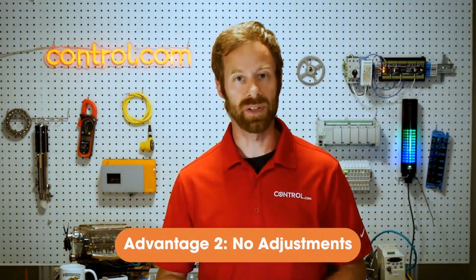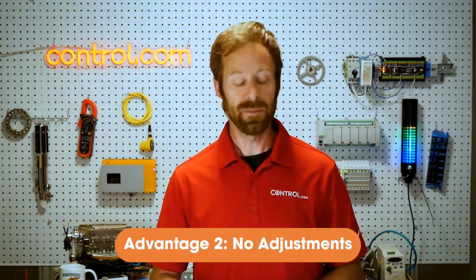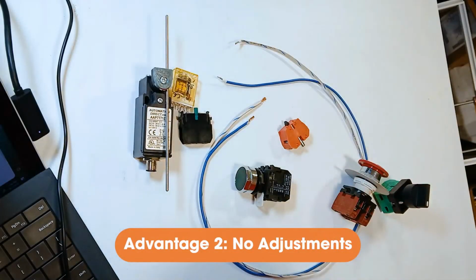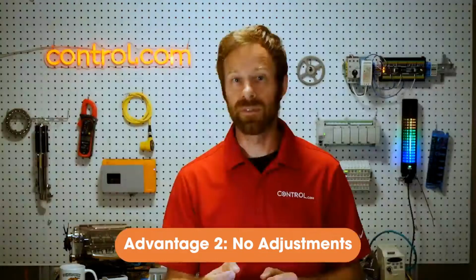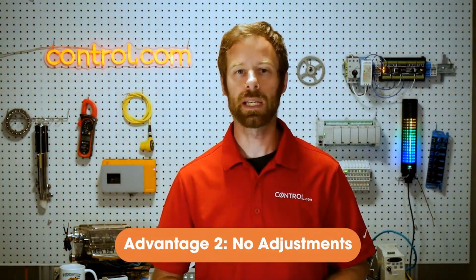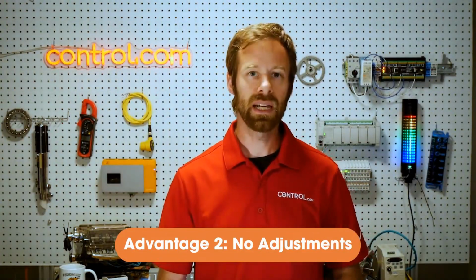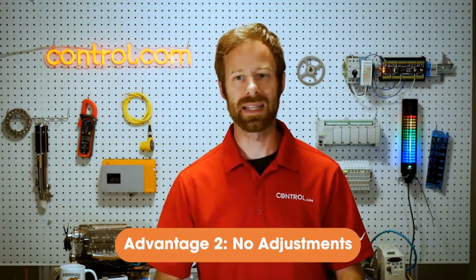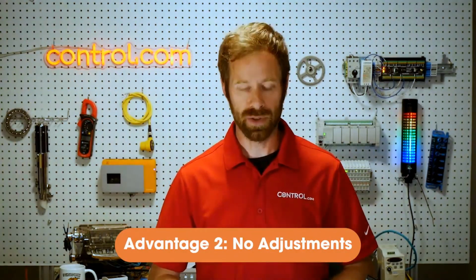Now, for some situations that may be a disadvantage, but for these electromechanical switches, it means that we can safely go to the storeroom, replace it with a drop-in component, and we don't need to worry about configuring any settings or adjusting any parameters. Just drop it in, and it's 100% consistent and never needs to be changed.